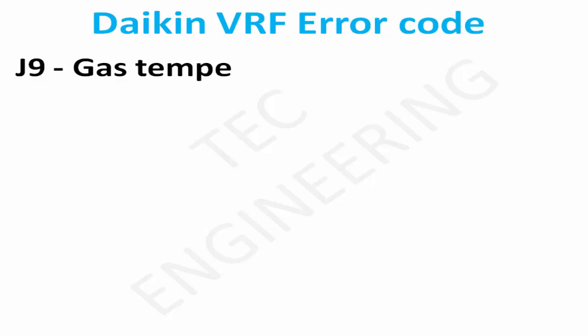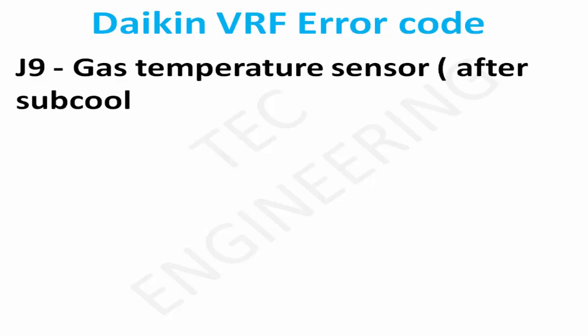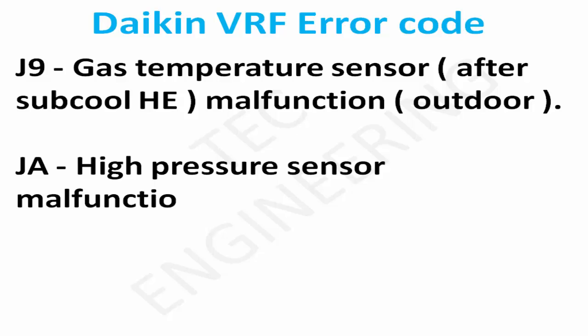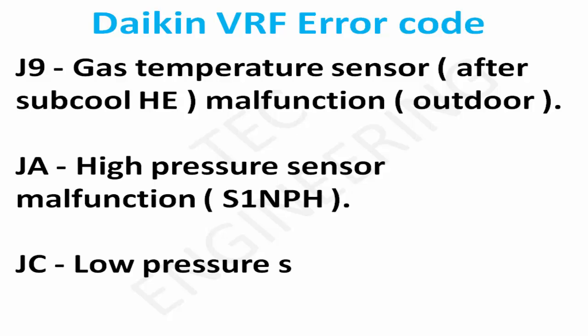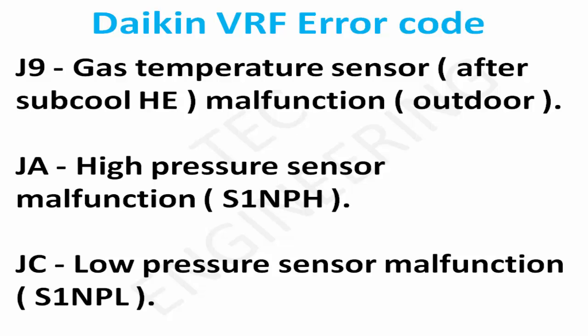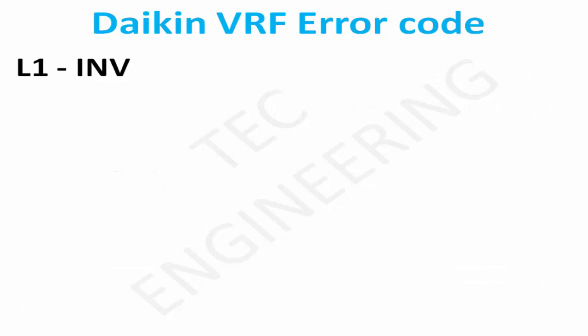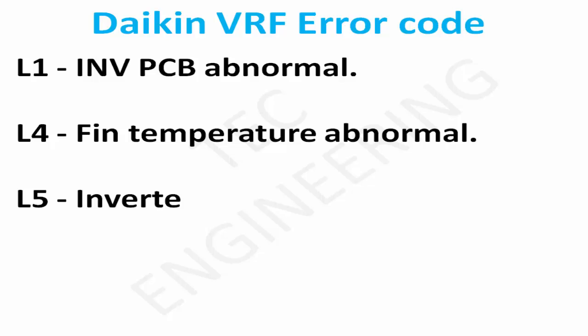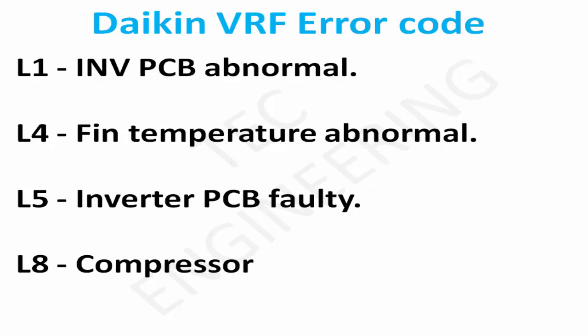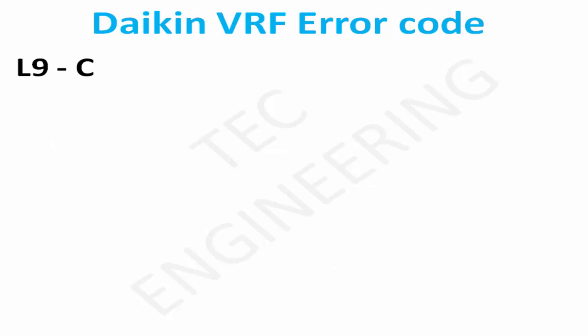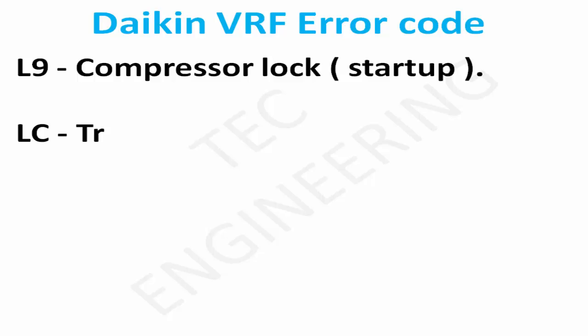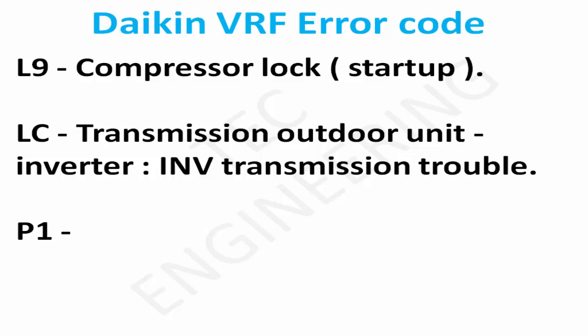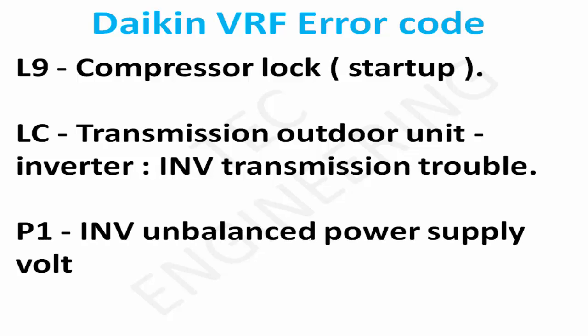J9: Gas temperature sensor after sub-cool HE malfunction, outdoor. JA: High pressure sensor malfunction S1 NPH. JC: Low pressure sensor malfunction S1 NPL. L1: INV PCB abnormal. L4: Fin temperature abnormal. L5: Inverter PCB faulty. L8: Compressor overcurrent detected.